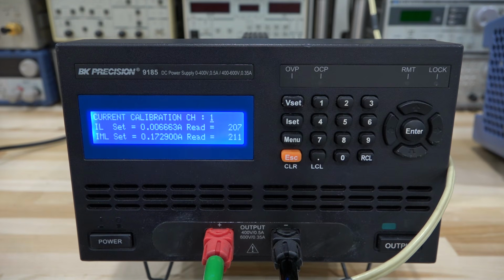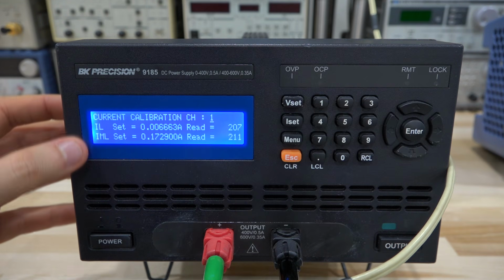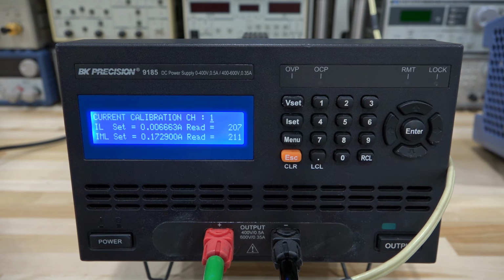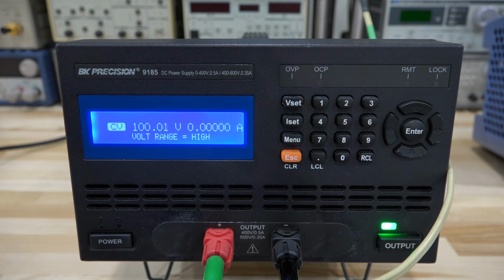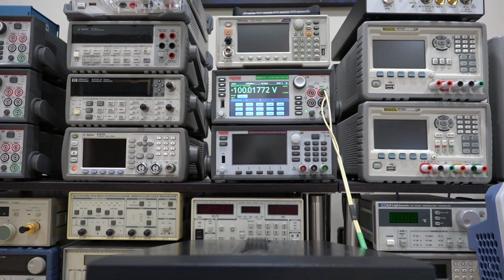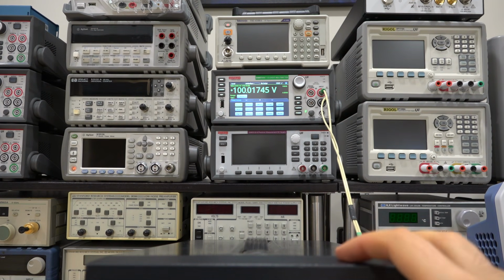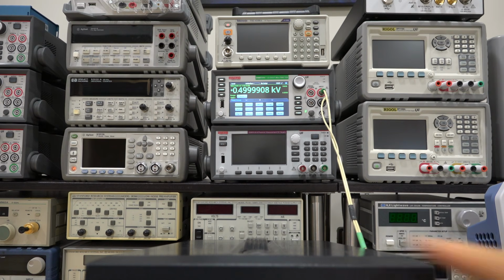And the current calibration process is essentially the same thing. We're just going to dump some current into the instrument and read it back. So I'm going to go through that also. It's pretty straightforward. And the calibration is done, and the numbers match. It's a little bit better than before. Not that it was very bad before, but it looks good. And I'm reading 100.01, and you can see up there we are reading about the same. So now if I set, let's say, 500 volts, I'm reading 499.98, and the instrument is reading about the same.